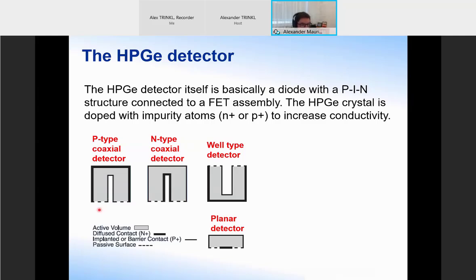And generally you have two electrical contacts. So you might have one type of electrical contact on the outside here. This is a p-type coaxial detector. So this is an N diffused contact, and then you have a P implanted contact on the inside. And on the opposite side, you might have your N-type detector, which is kind of the reverse, where the electrodes are reversed. So you have the P contact on the outside, the N contact on the inside.